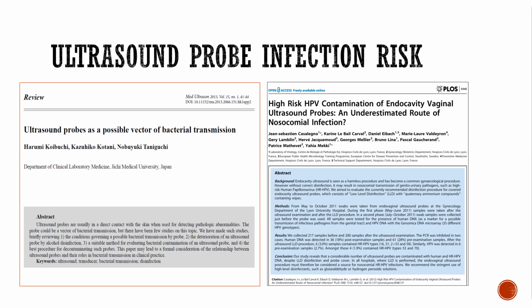These particular authors felt that the deterioration of the probe and then inadequate disinfection were contributing factors.